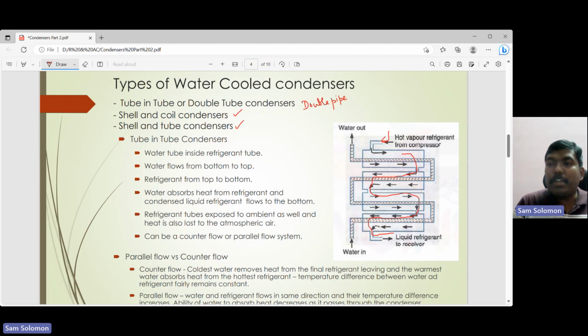And it also follows your natural convection principle, wherein when water absorbs heat, its density becomes a little bit less, and so it is easy for the water to rise up. Obviously it is not going to rise up on its own; you are going to use a pump to do that. The water flow is from bottom to top and the refrigerant flow is from top to bottom. Okay, and that is what is mentioned over here.